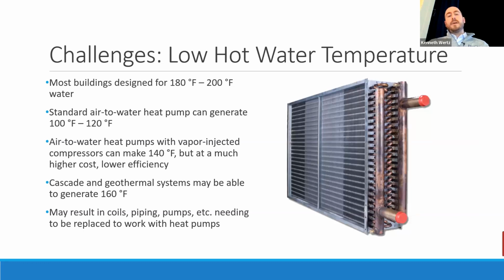So I mentioned earlier, the heat pumps produce hot water as opposed to hot air. A common struggle is that they can't produce as hot a water as a boiler can. Most boilers can put out anywhere from 180 to 200 degrees to heat the building. Heat pumps, in the most standard configuration, can do like 100 or 120 degrees. So that big difference, it's not hard to see how that can mean that you're having a hard time keeping your building warm with that lower temperature.